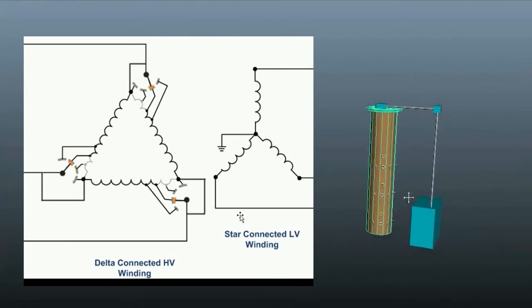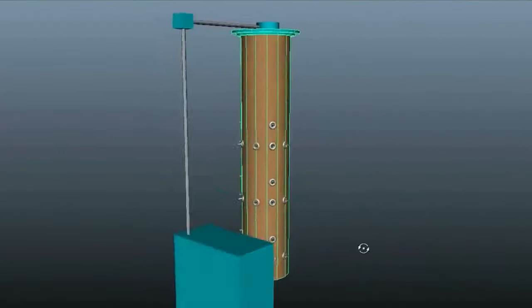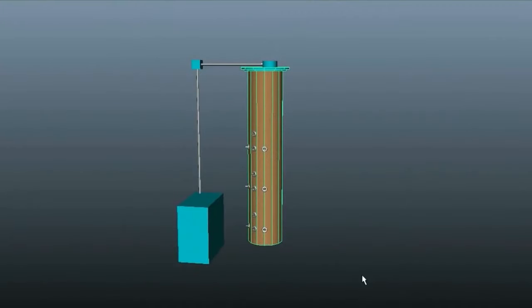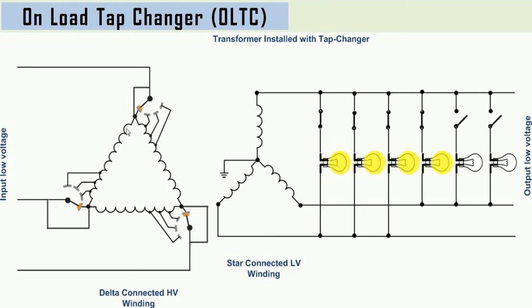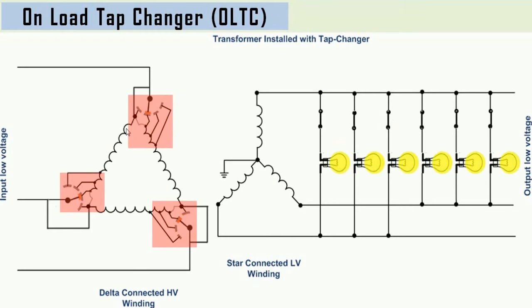From the name itself, it is clear that OLTC helps in changing the taps of the transformer during on-load condition. Now the question is, why is it necessary to change the position of taps in the transformer? This is because when power or distribution transformers get loaded, their terminal voltage gets reduced due to internal voltage drop in the impedance of the winding. Similarly, when the load on the transformer is reduced, its terminal voltage exceeds the expected value. This variation of terminal voltage due to variation of load is known as voltage regulation.